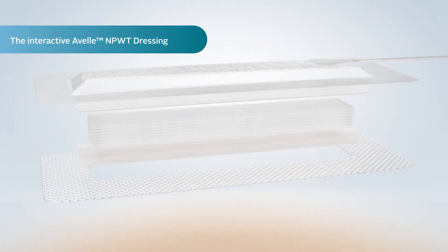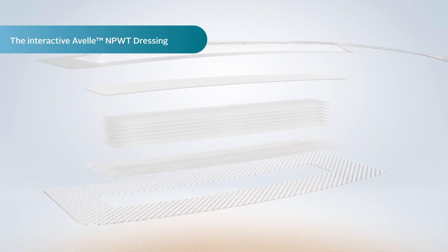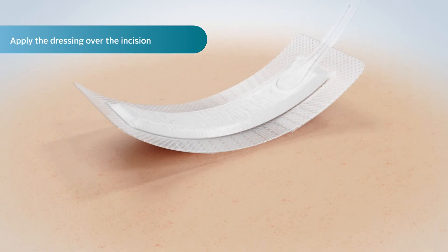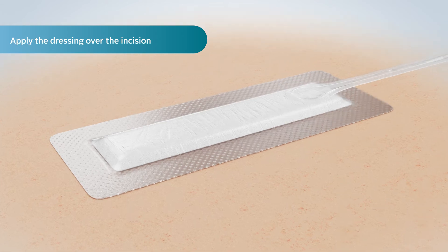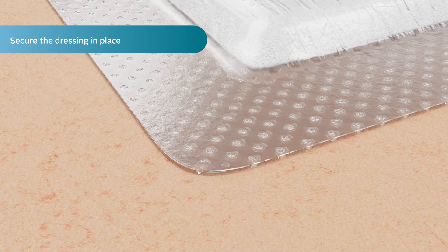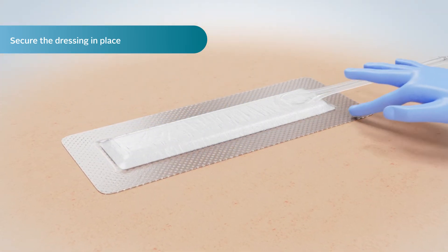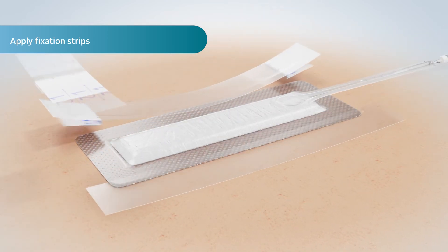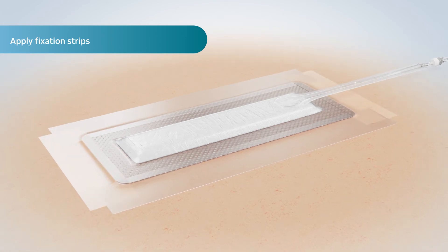The Avelle dressing includes a Hydrofibre Technology interface, which has many clinical benefits and has been engineered to deliver negative pressure to the wound. On application, the Avelle dressing should be positioned with the port over intact skin and uppermost from the incision. The perforated silicone adhesive borders secure the dressing in place while being gentle to the skin during removal. Ensure the border is smoothed out to minimize air leaks. Fixation strips can be applied with a 1 cm overlap to all sides of the dressing in order to maintain the seal during the wear time of the dressing.